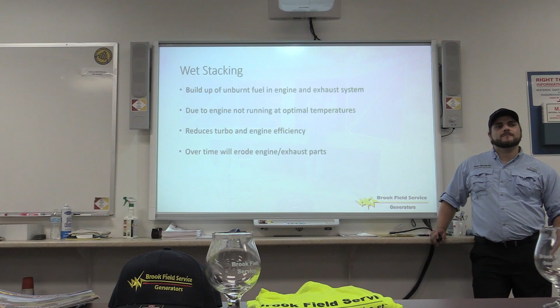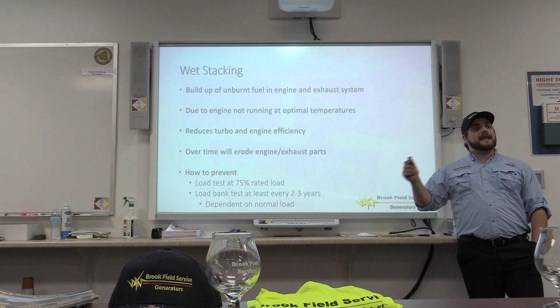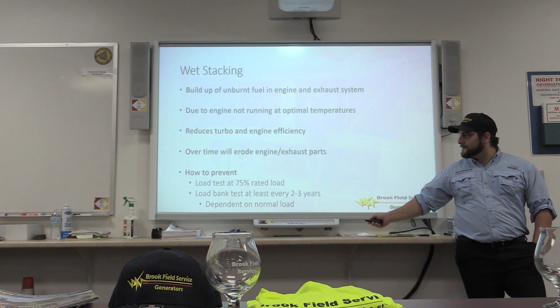Gotcha. And NFPA 110 does have guidelines, which I'll jump into in a second, about diesel load bank testing and obviously the avoiding of wet stacking. As we just mentioned, to prevent it, load test at 75% rated load, as Josh was saying. Do that once per month. That will ensure you're building those temperatures to burn off that unburnt fuel. We also recommend load bank testing at least every 2 to 3 years. NFPA 110 says for diesel engines it's every 3 years, and obviously that is dependent on the normal load for other non-Level 1 systems.